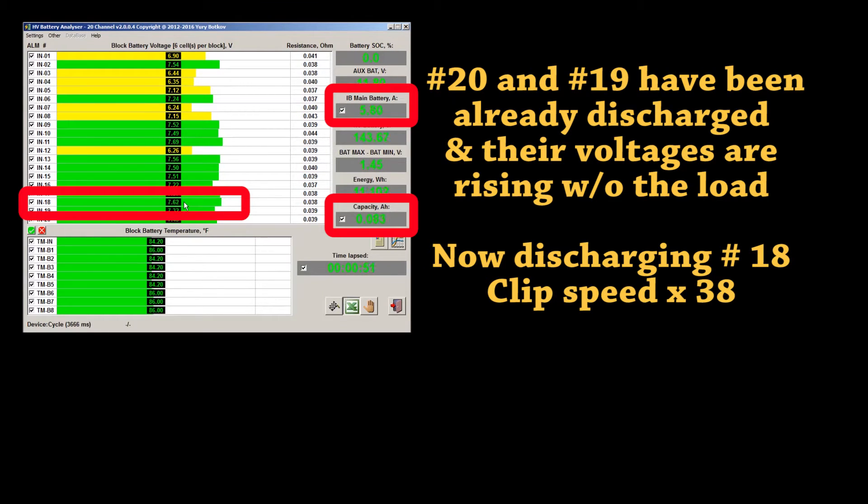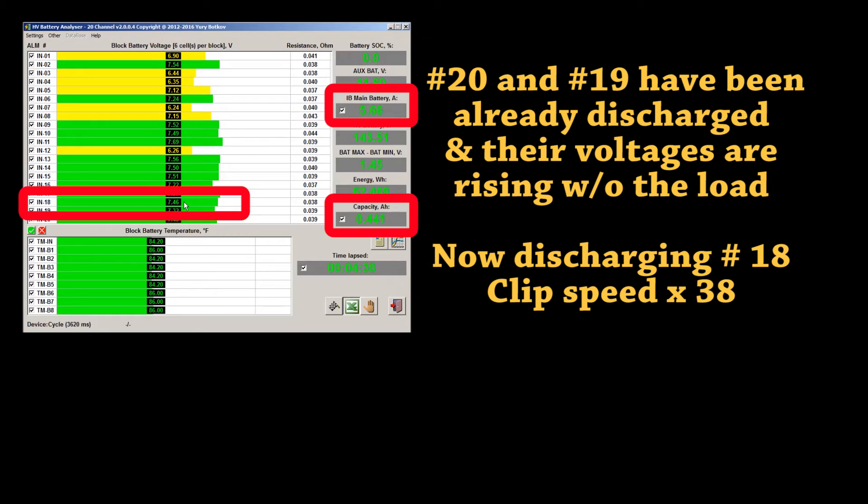Number 20 and 19 have been already discharged, and the voltages are rising without the load. Now we are discharging number 18.